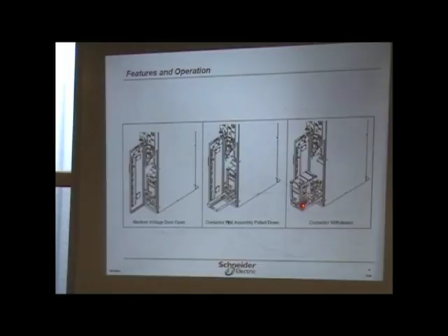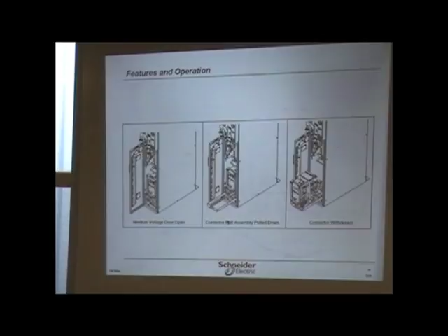So you can troubleshoot this, close that back up again, lock it up and everything else, and troubleshoot the contactor and find out if it didn't close or the contactor didn't pick up. You can apply control voltage, because you've got a voltage control transformer on there, and you can do that externally instead of trying to do something in here and find out if the problem is here or there, right? Versus trying to do this with the power energized. So there are ways of doing this safely. That's that isolating means that we were talking about a little while ago.